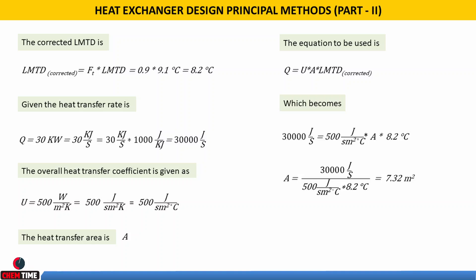The heat transfer rate Q is 30 kW = 30,000 W. The overall heat transfer coefficient U is 500 W/m²·K. Using Q = U × A × LMTD_corrected, we get 30,000 = 500 × A × 8.2. Solving for A, the heat transfer area is 7.32 m².